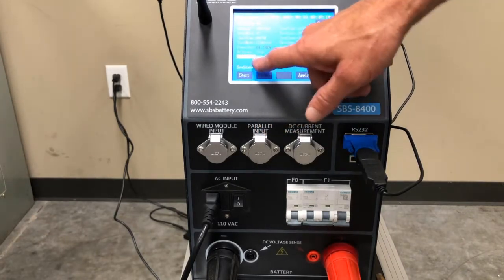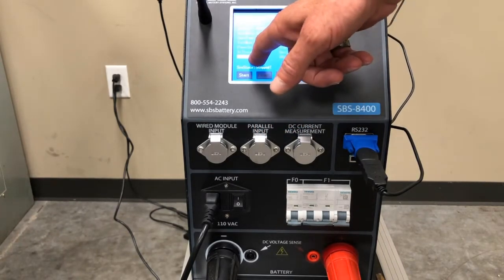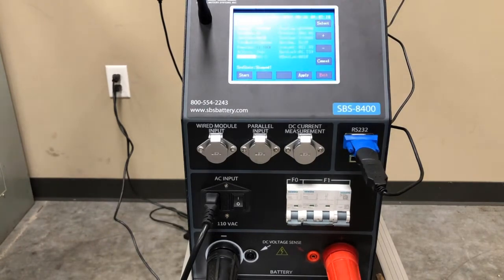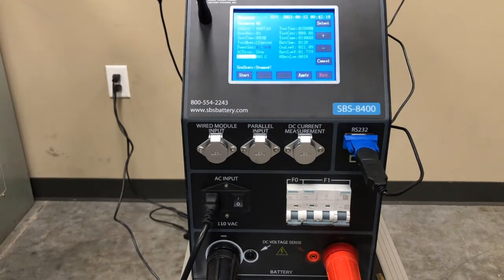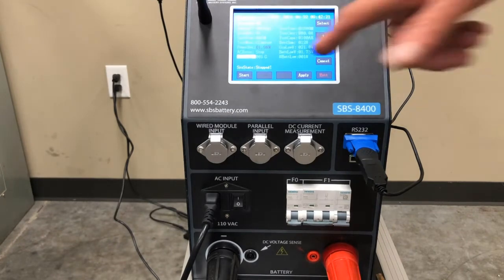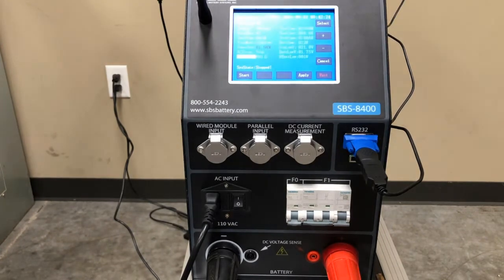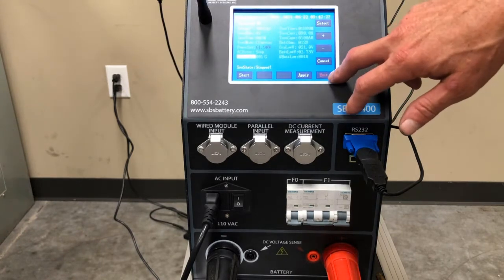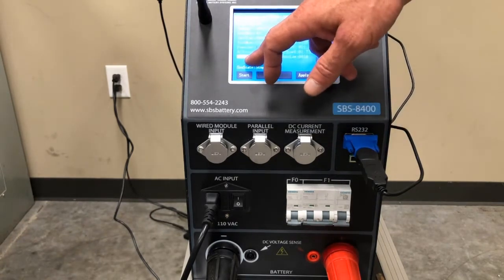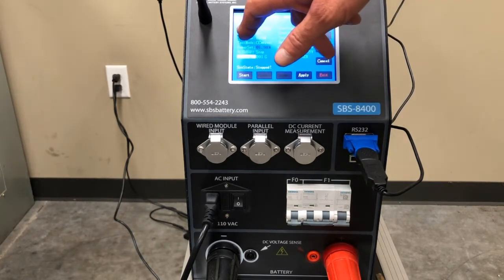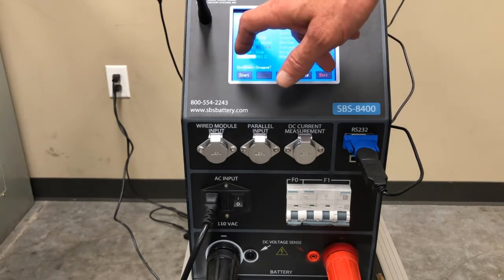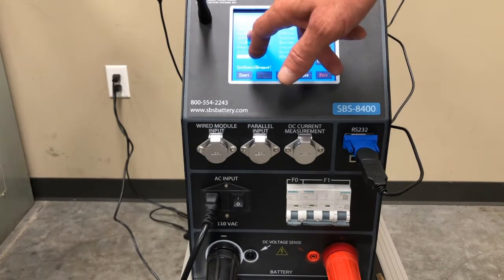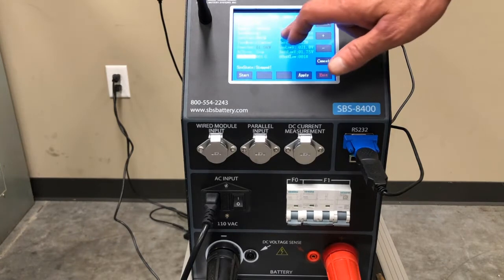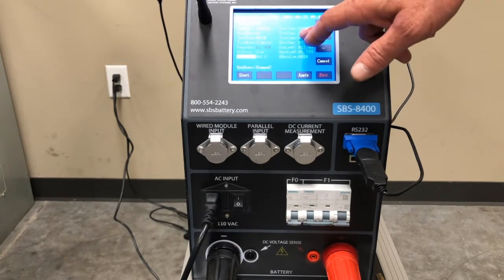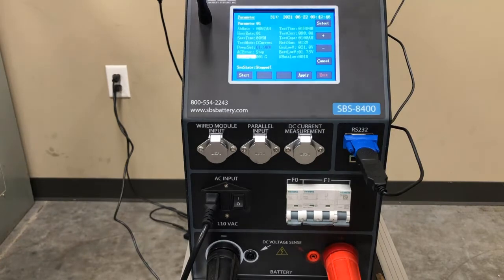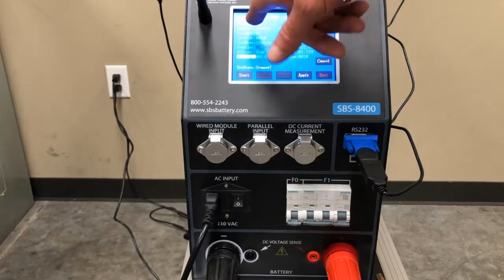I'm testing one string. So I can test multiple strings of batteries at the same time. The wireless modules will connect to one string and two strings. And then I just set that value to 2 if I'm testing 2 batteries at the same time. If I'm testing 2 batteries at the same time, I've got to remember amp hour rate doesn't change, hour rate doesn't change because the batteries are still rated the same, but my discharge current, my test current, I've got to double because now I'm pulling 2 strings, and each string I want to run at its rating.